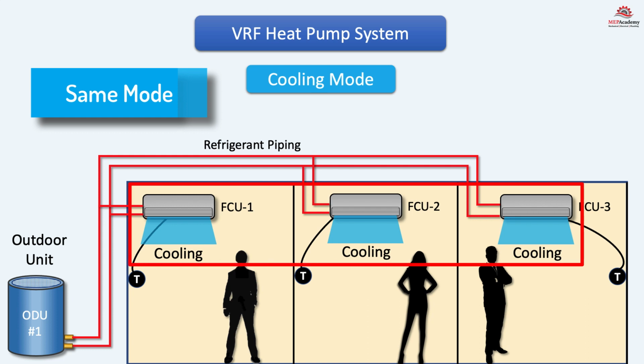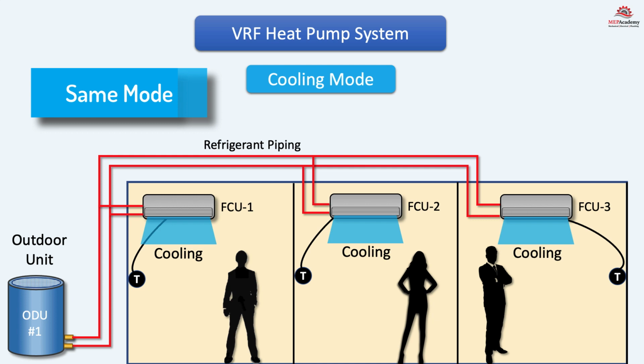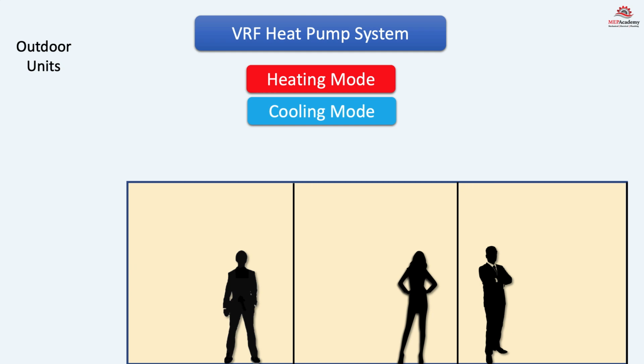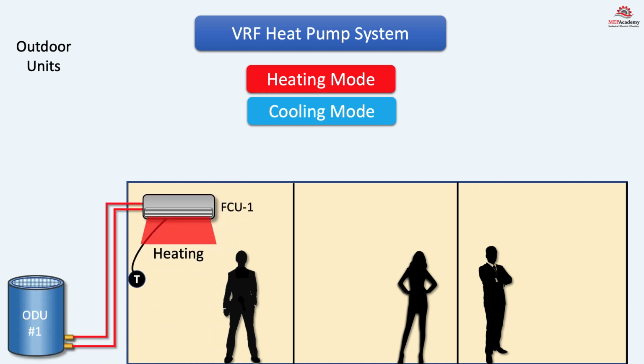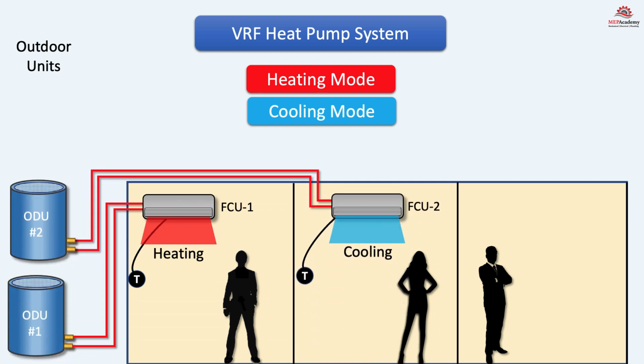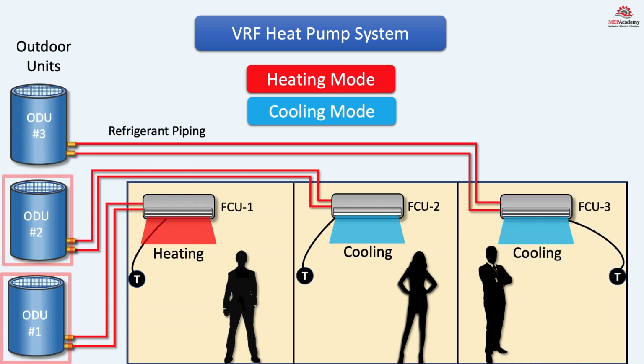With a VRF heat pump system, if each zone or office wanted to control whether to heat or cool their space, then each would require their own outdoor unit. Here we have an executive in office number 1 wanting heating, while the second office wants cooling. Each indoor fan coil will require a separate outdoor unit, and the third office is also calling for cooling and will have their own outdoor unit.